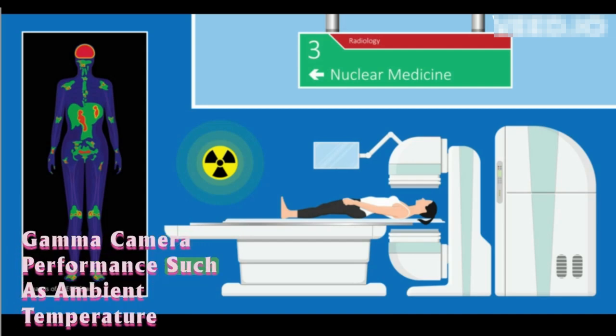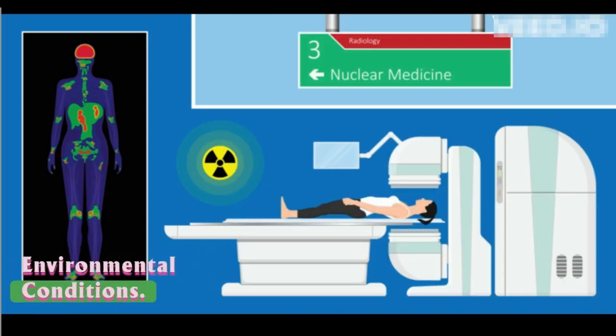Environmental factors: Consider environmental factors that may affect gamma camera performance, such as ambient temperature, humidity, and electromagnetic interference. Ensure that the gamma camera is operating within the recommended environmental conditions.